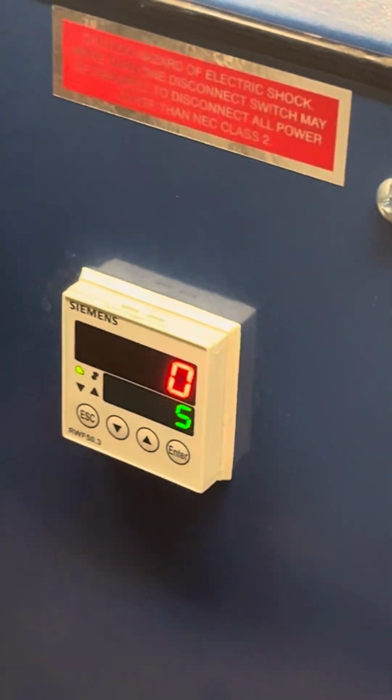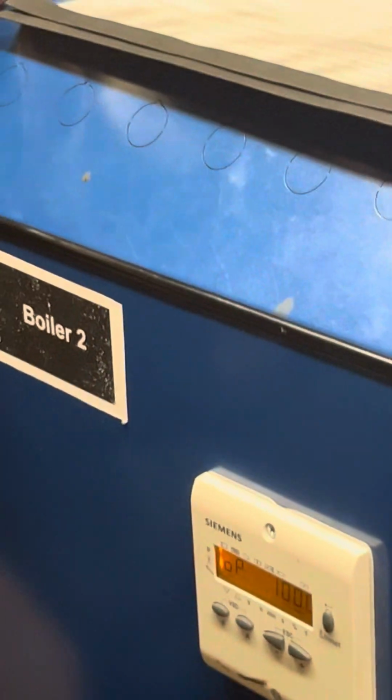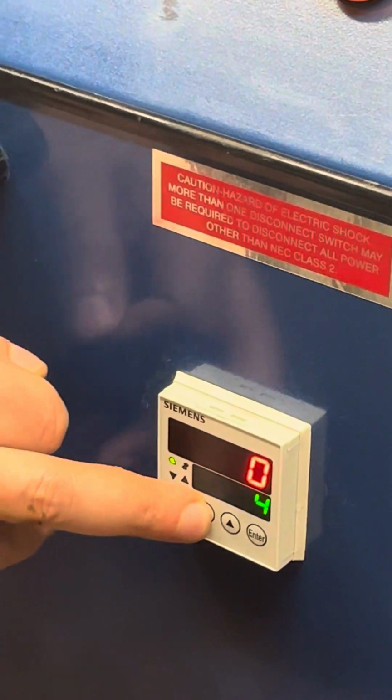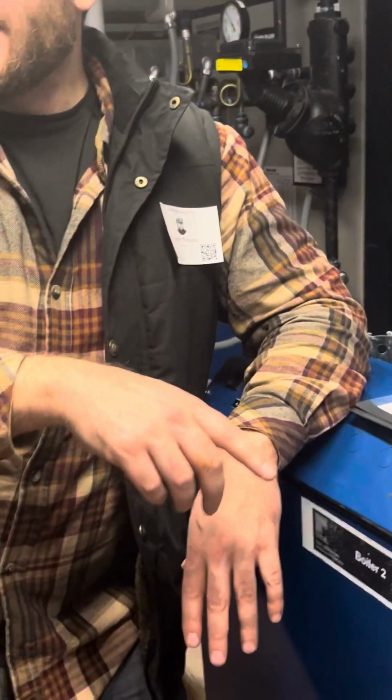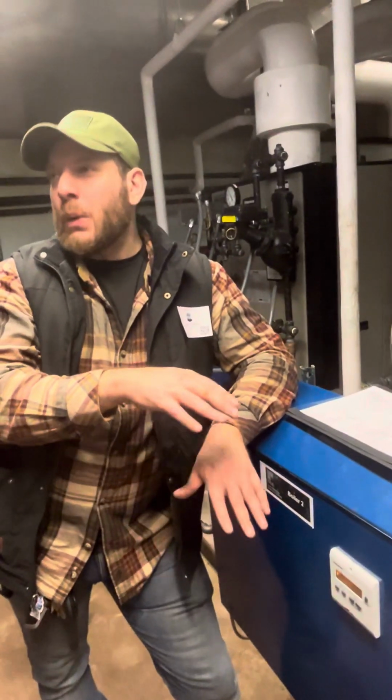But it's not going to shut the burner off there. It's going to shut the burner off 2 psi above that set point. If you did set it at 2, it's going to shut the burner off at 4. So we're using this more for modulation. It can and will shut the burner off, but that's not what we want to do.